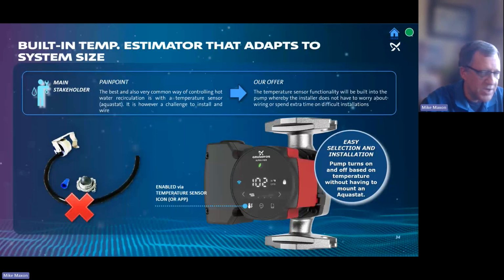So we don't need to wire an aquastat anymore because we are sensing the water temperature. It's a temperature estimator. And on this front screen, you can see here that we could actually read on the pump what the fluid temperature is. That's actually the default. If we touch the button here, we could see what the wattage of the pump is and what the flow rate is. But being able to see the temperature, I think, is a great thing. But this aquastat that it has built in, if we go into the app, we could set either the temperature on or the temperature off, or we could set it for a temperature that we want to maintain.